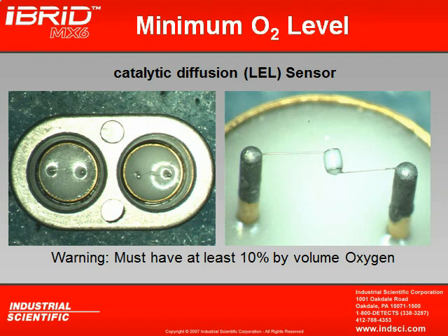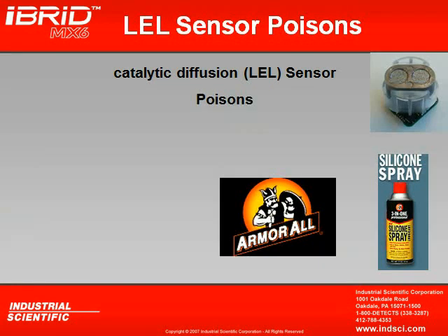The thing about combustible sensors though, since it works on the principle of burning combustible gas, we have to ensure that we have at least 10% by volume oxygen available. Otherwise, the combustible sensor will either not detect or read erroneously low of combustible gases. Now, the combustible sensor inside your instrument should give you about 3 to 5 years of life. But a poison can shorten that to 3 to 5 months if we're not careful.